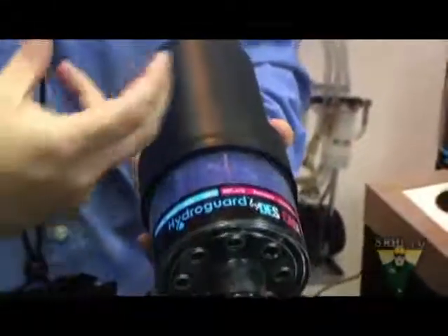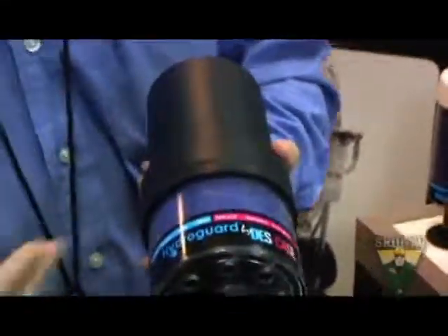Well, that air is whatever the plant air is, and which is typically dirty and or humid. And the typical OEM vents are not the highest quality. They're not designed to stop low levels of particulate and moisture contamination. So what we have are tools, specifically breathers, so that when you do ingress air into your system, only clean and dry air comes in. Breathers have fine particulate filter, typically down to either 3 or 1 micron absolute, as well as silica gel to stop the humidity from coming in as well.